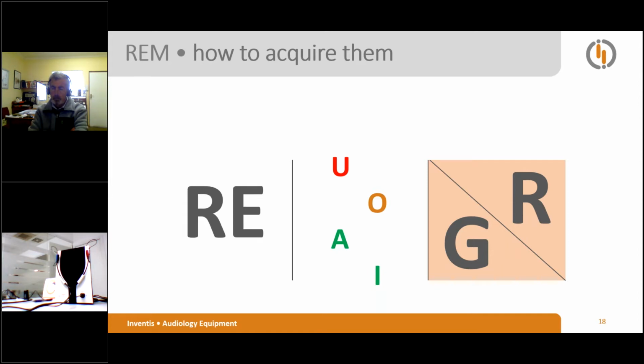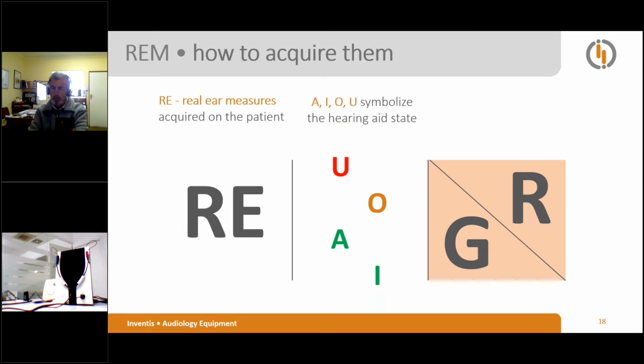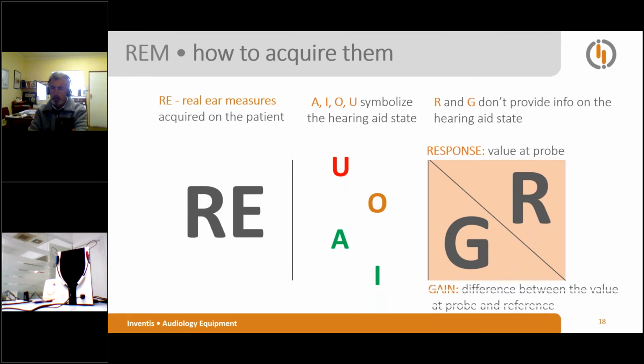How to acquire? We can continue. So, real ear measurement acquired on the patient. The REM system allows the operator to acquire many types of measurement defined in ANSI and IEC standards and classified in response measurement or gain measurement. I didn't tell you, but it is quite banal. U stands for unaided, O for occluded, A for aided, and I stands for insertion, real ear insertion measurement. So the hearing care professional can perform a response or gain measurement.